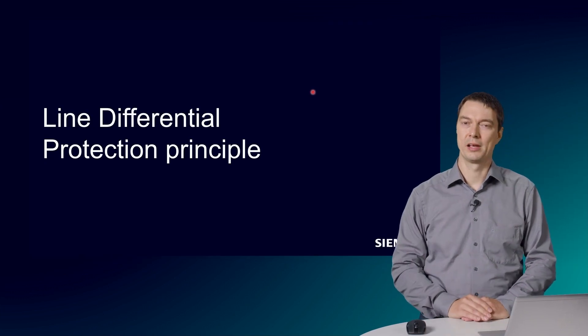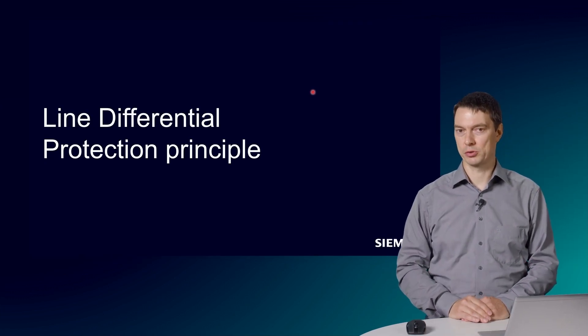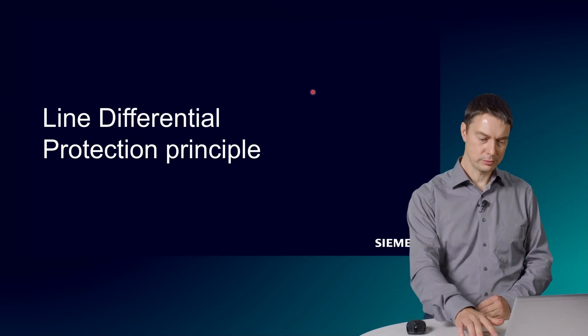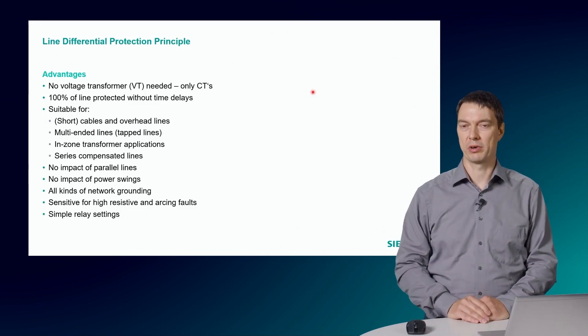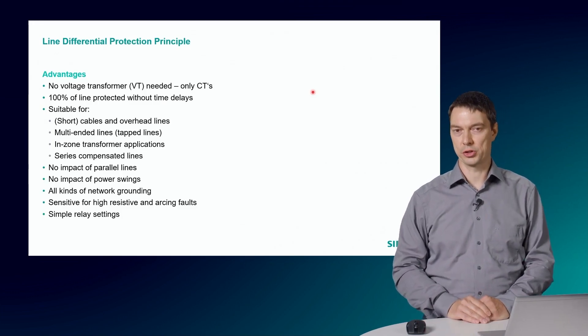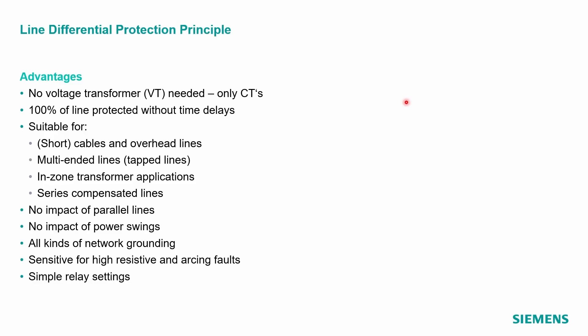Let's come to the Line Differential Protection Principle. The Line Differential Protection Principle provides the following advantages. It only requires CTs. There is no need for a voltage transformer. It's a unit protection. So 100% of the line is protected without an additional need for a time delay.